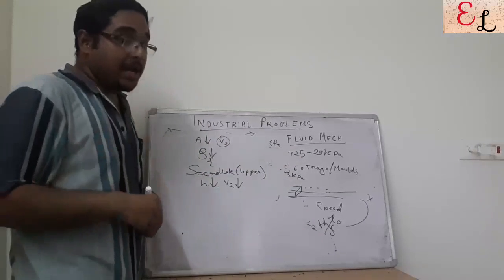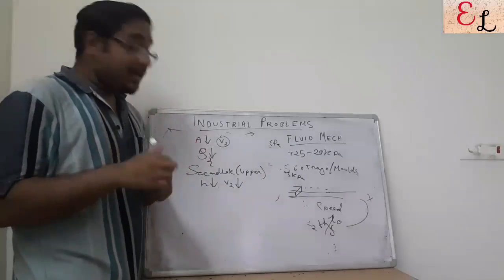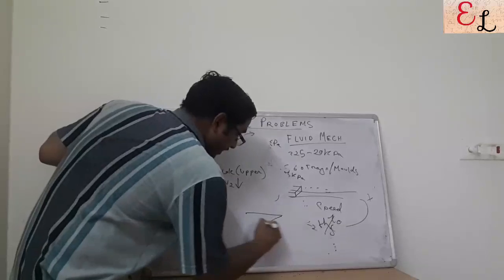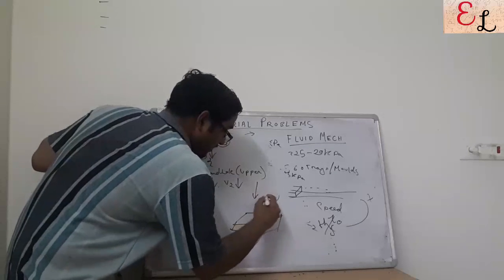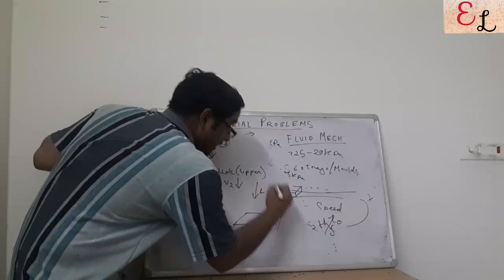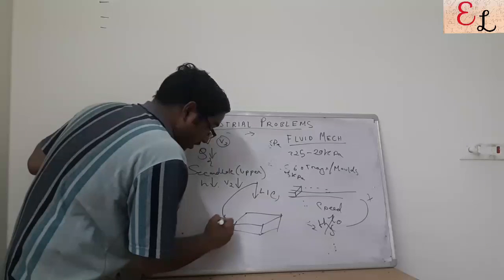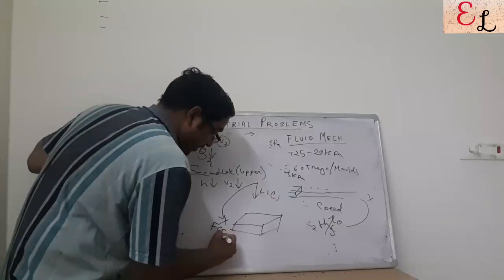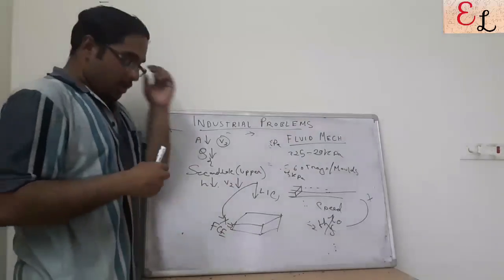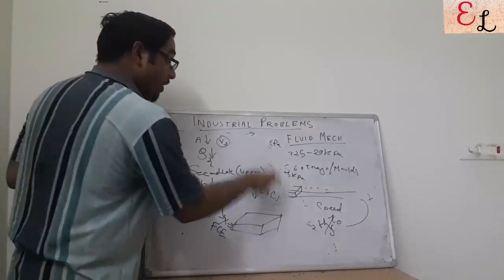The third idea is to fit in a motor such that it is level controlled. So this particular mold will have a level indicator transmitter, LIC, that is a level indicator controller, which will hence control with a final control element, FCE, the motor speed. Once the level is full, it would actuate the motor, and the motion will be continued according to the level.